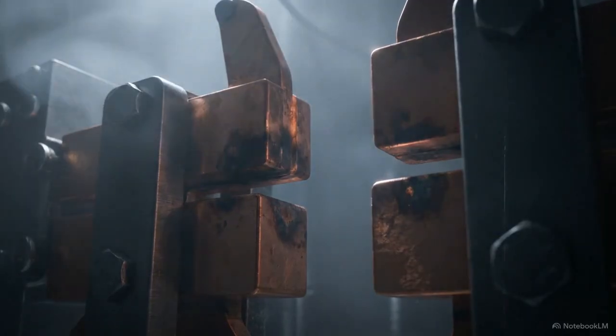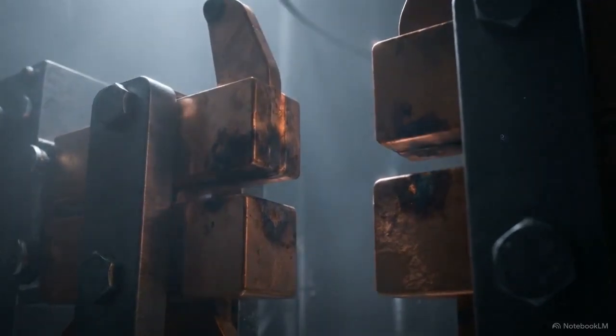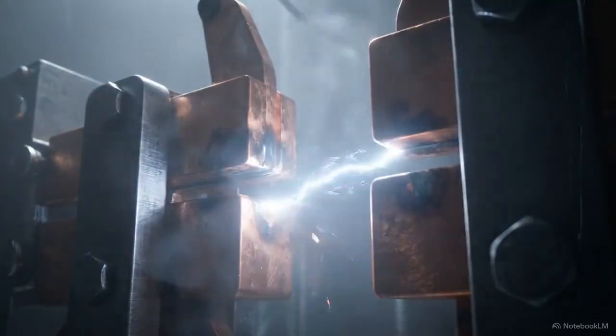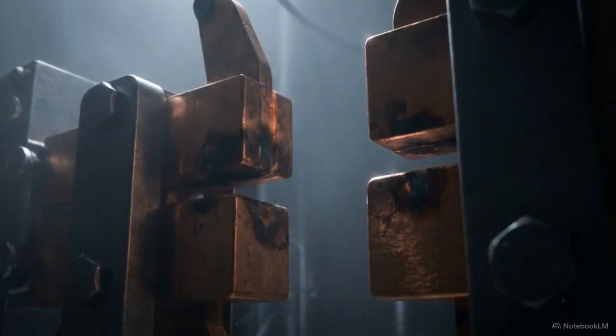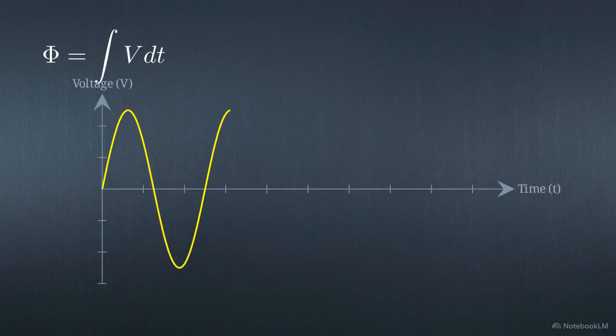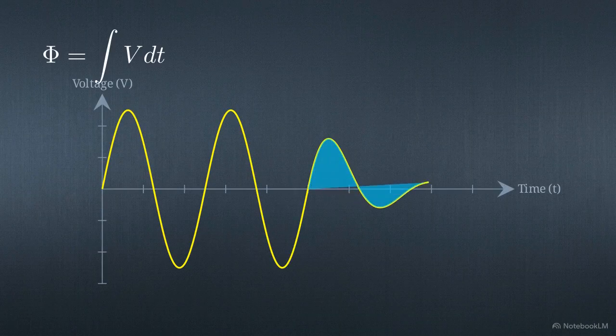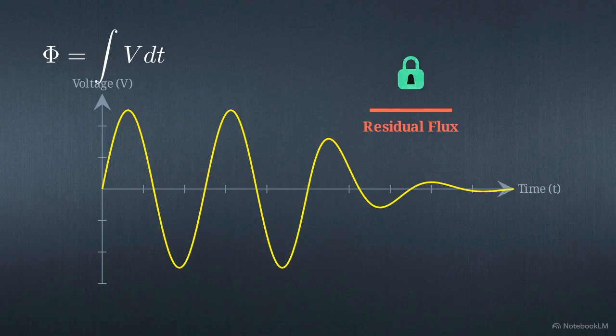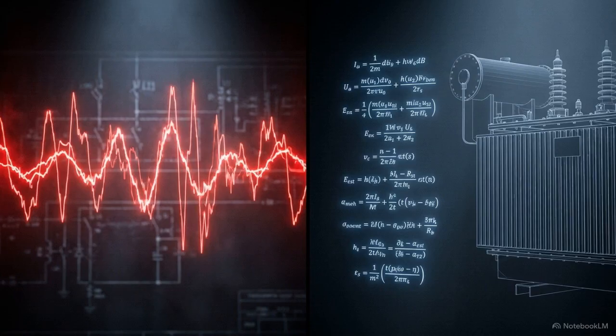It actively watches the decaying voltage at the transformer's terminals at the exact moment the machine is shut down. This chart shows that mathematical calculation in action. By integrating the dying voltage wave, the controller calculates the exact magnitude of the trapped residual flux. It locks this value into memory, waiting patiently until the command to restart is given. By mapping the invisible threat beforehand, a dangerous game of chance becomes a predictable, solvable equation.